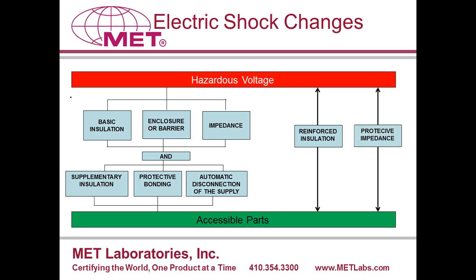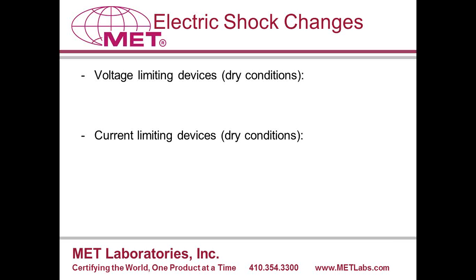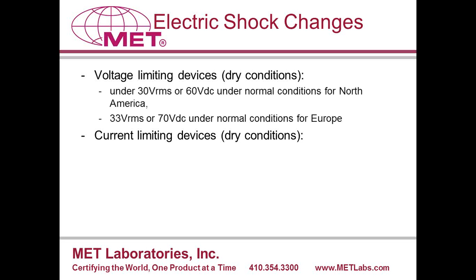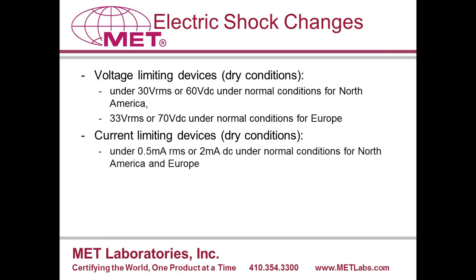The third edition has now added a fourth means of secondary protection, a voltage or current limiting device which together with the primary protection can protect accessible parts from hazardous voltage. Here are the voltage and current limits that a limiting device must meet. They're spelled out more completely in Clause 6.3.2 of the standard. Voltage limiting devices must reduce the voltage to less than 30 VRMS or 60 VDC for North America. Current limiting devices must reduce the current to less than 0.5 milliamps RMS or 2 milliamps DC.